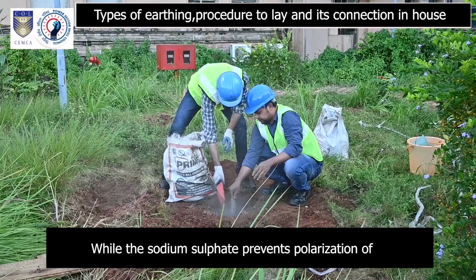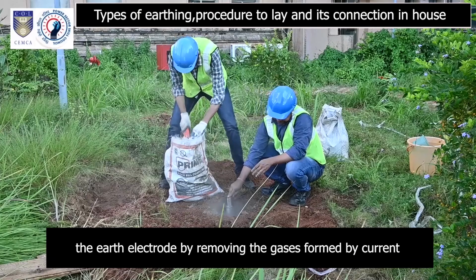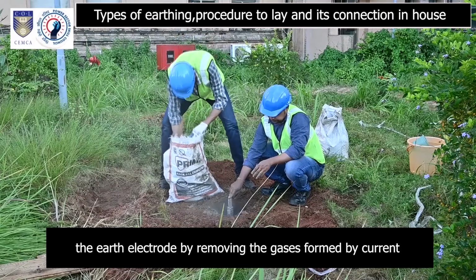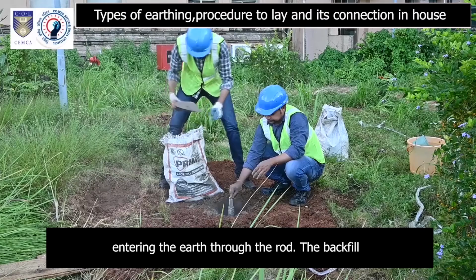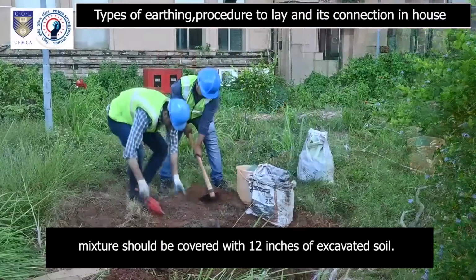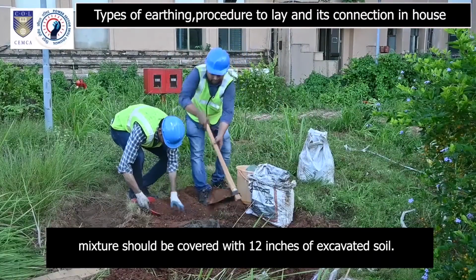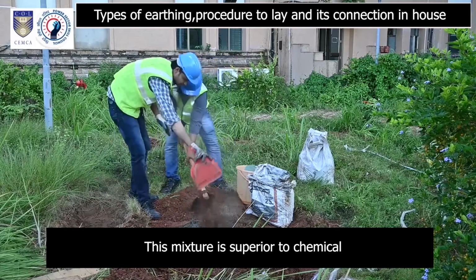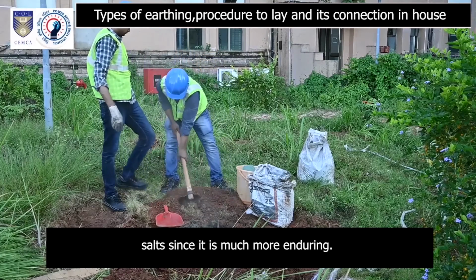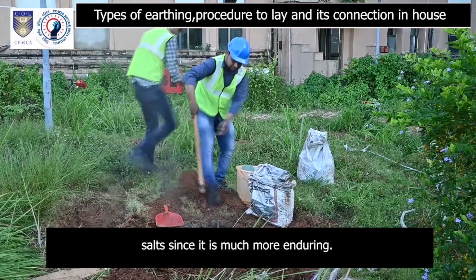While the sodium sulfate prevents polarization of the earth electrode by removing the gases formed by current entering the earth through the rod. The backfill mixture should be covered with 12 inches of excavated soil. This mixture is superior to chemical salts since it is much more enduring.